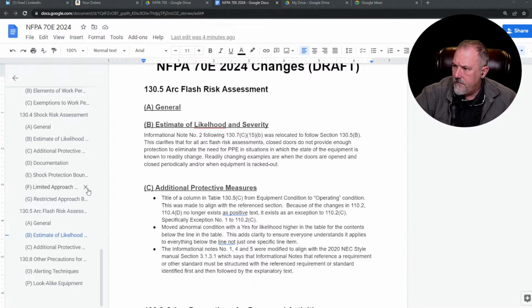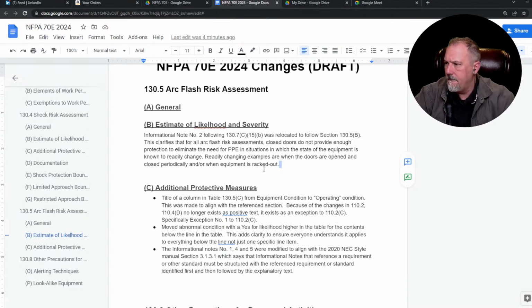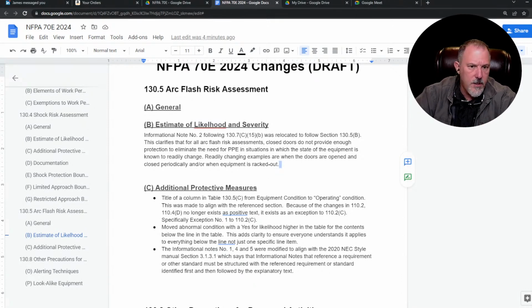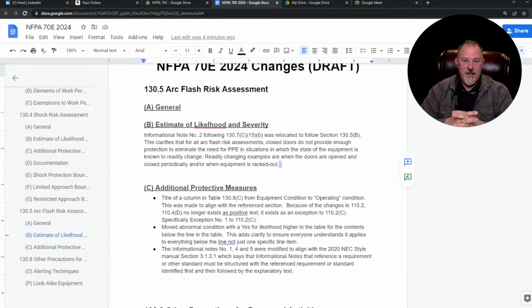I'm going to say, really, because it says readily changed. Example, doors open or closed, rack in or rack out. Oh, so if you open the door, that's a readily changing situation. Well, but then I know it doesn't make sense because if I open the door, the door can't provide me protection because it's opened. I have to open the door in order to activate the thing. The rack in and rack out, his situation there, it makes sense to me because you're changing the state of the power system. You're either racking it in or racking it out. Opening a door on a panel does not change the state of anything.